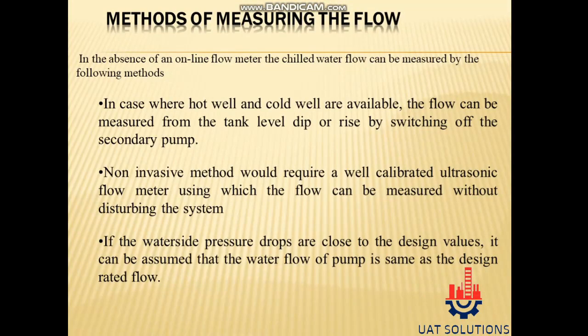Methods of measuring the flow. In the absence of an online flow meter, the chilled water flow can be measured by the following methods. In cases where hot well and cold well are available, the flow can be measured from the tank level dip or rise by switching off the secondary pump. A non-invasive method would require a well-calibrated ultrasonic flow meter, using which the flow can be measured without disturbing the system. If the water-side pressure drops are close to the design values, it can be assumed that the water flow of the pump is the same as the design rated flow.